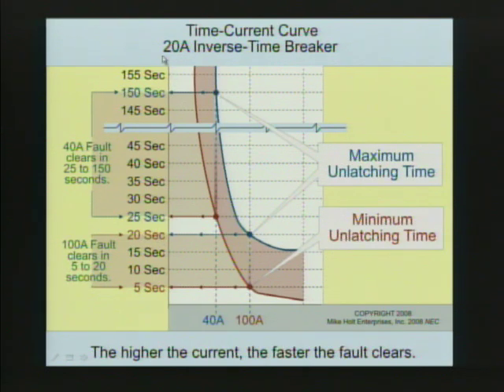So a 20 amp breaker having 5 times its rating under a fault condition. Now we're talking about RMS, right? We're not talking peak here, which would be a lot greater than that. Let me put this in perspective. If you have a 20 ampere circuit and it's not AFCI protection, and you had a 100 ampere RMS, which the peak of that would be about 140 amperes peak, it would take 5 to 20 seconds. Can you imagine how much heat, how much energy? The possibility of fire is huge.